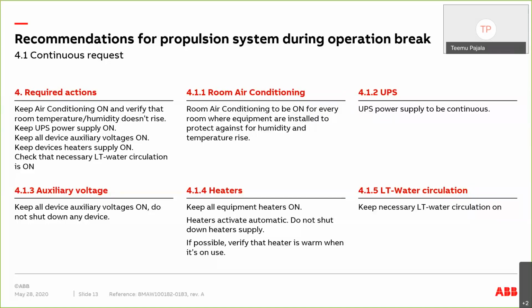As a continuous request, the room air conditioning should be checked to confirm that it's on. It's a normal routine in general on vessels, of course, but it should continue also in the layup condition, to make sure that in case of failure there is no area left without air conditioning. UPS power should be on. Auxiliary voltages, like mentioned, should be on. Heaters and LT water, everything should be running as normal. Of course, consumption is less, so there should not be too much worry about energy efficiency in the auxiliary or UPS power, because there is not much consumption ongoing when the vessel doesn't operate.